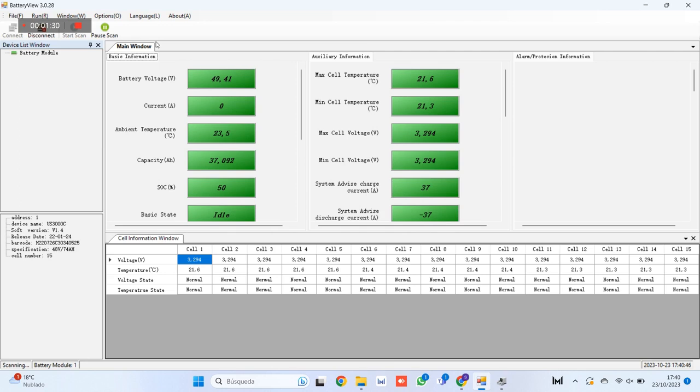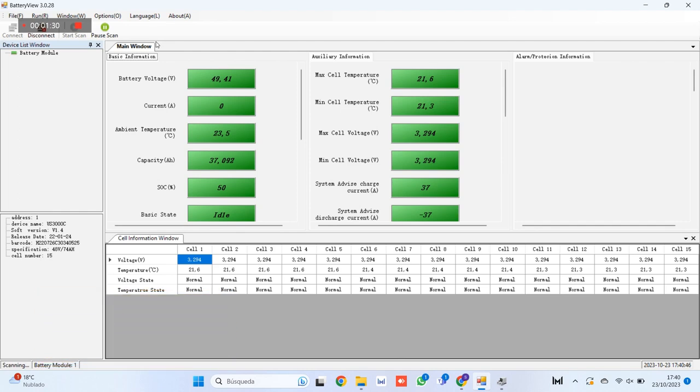Step number 7. And lastly, thanks to this monitoring system and the registration of data, or commonly called logs, it will be possible to see the use that has been given to the battery, the number of life cycles that our battery has, and any incidence to determine if the battery has suffered a failure out of guarantee or not.